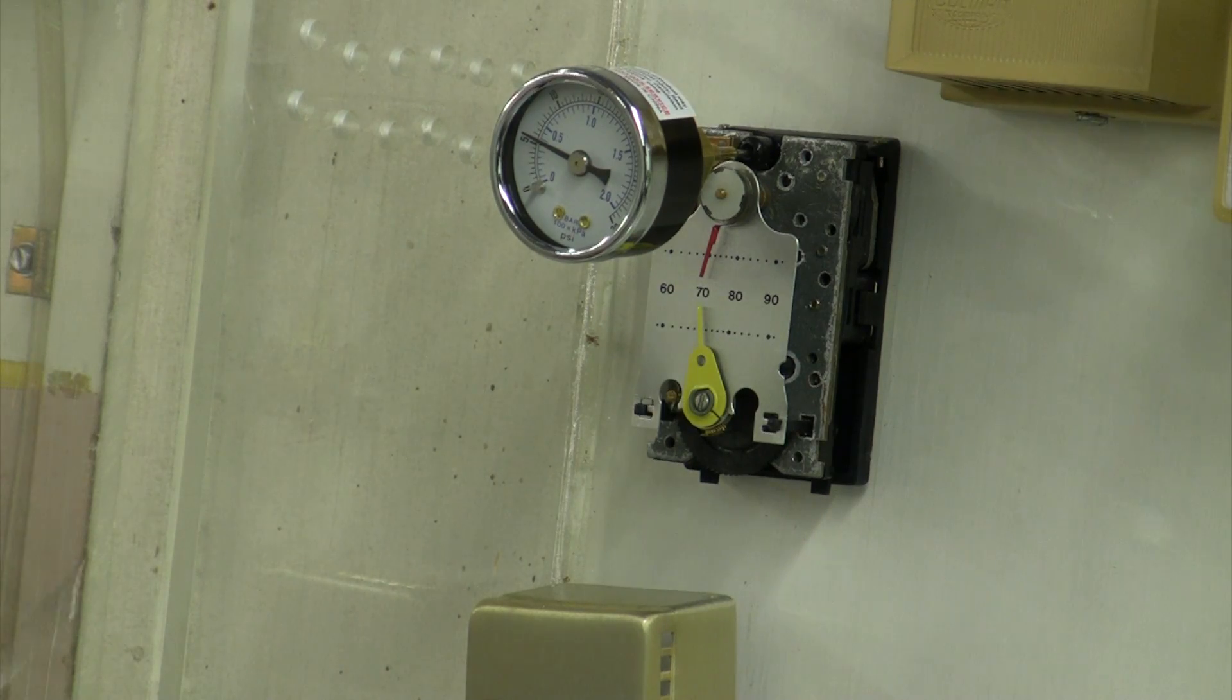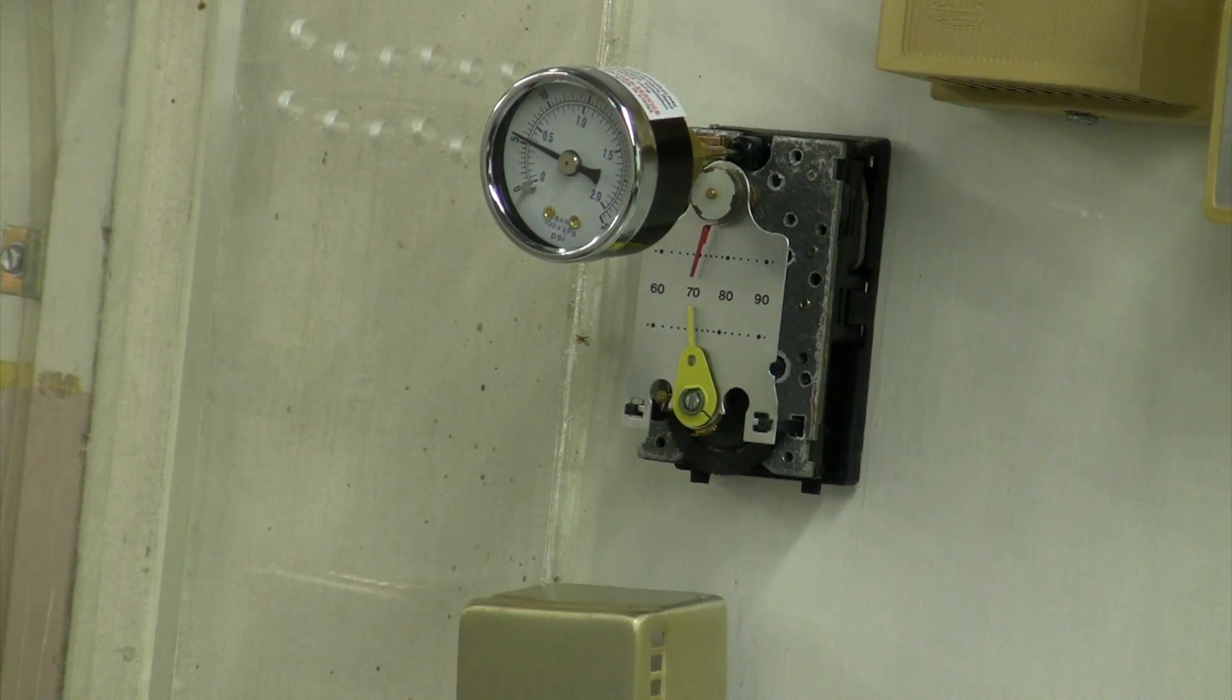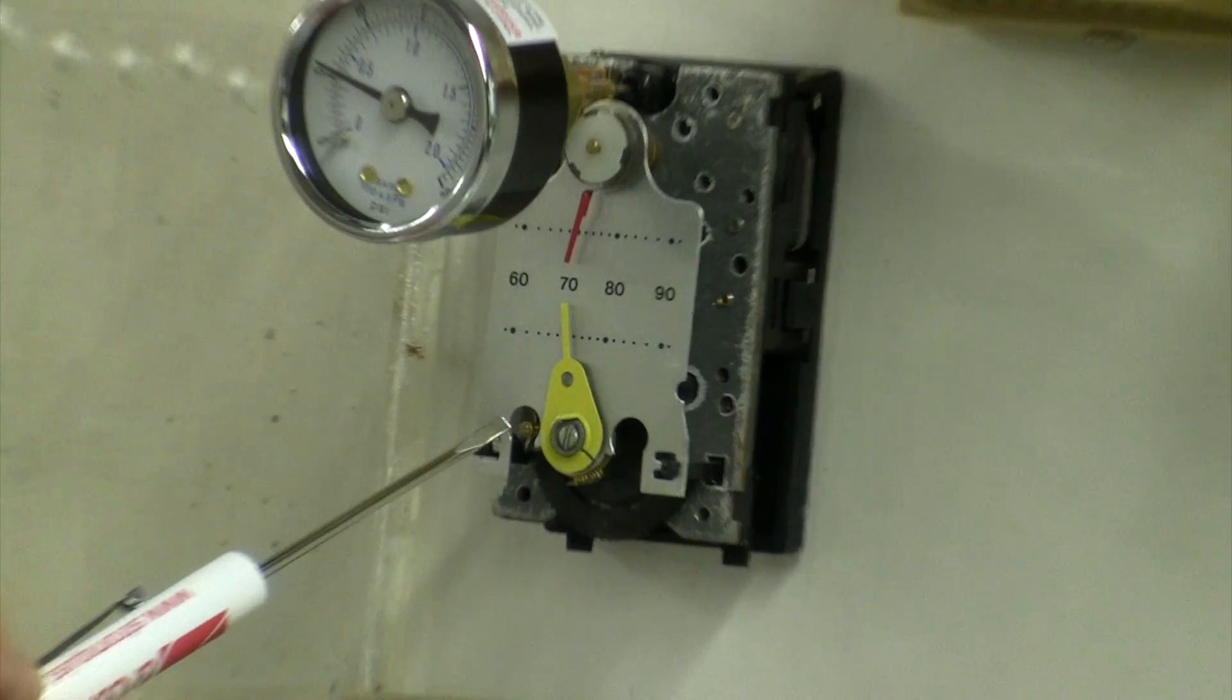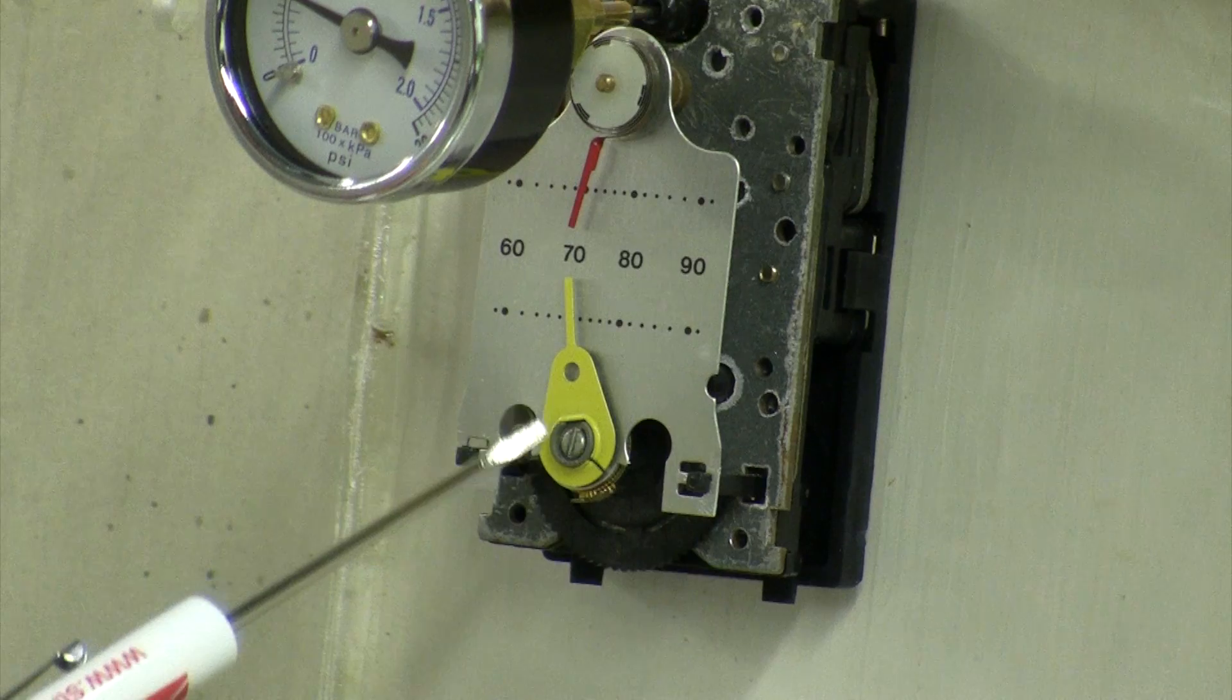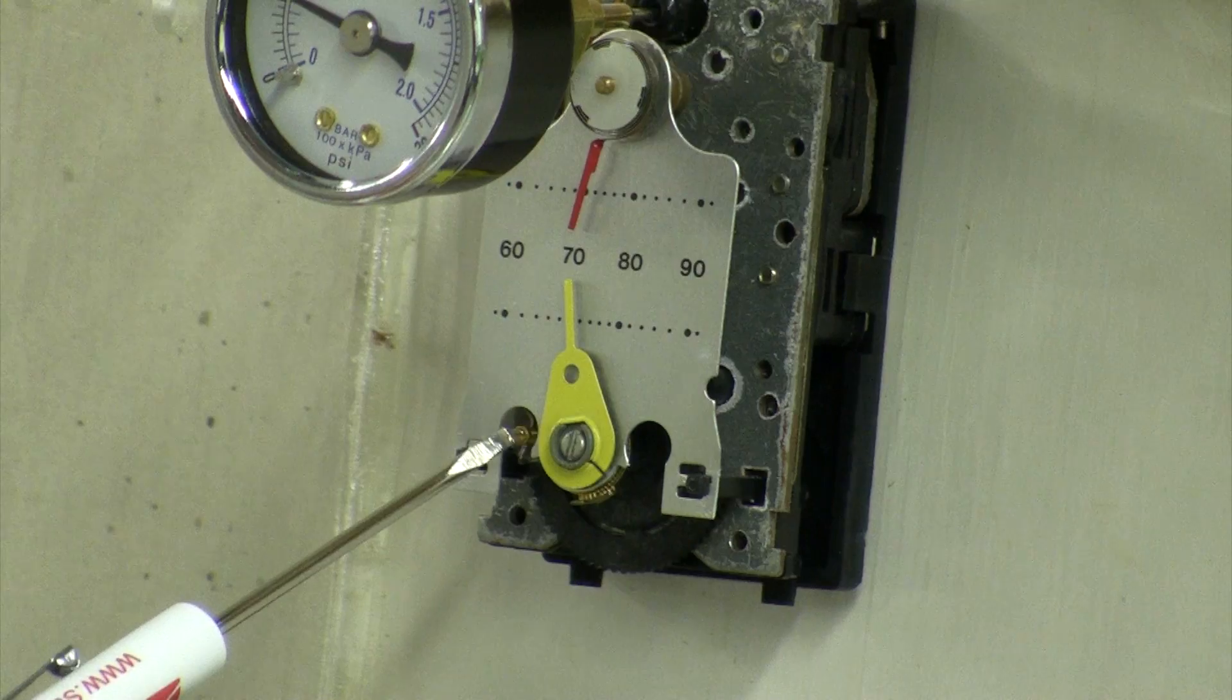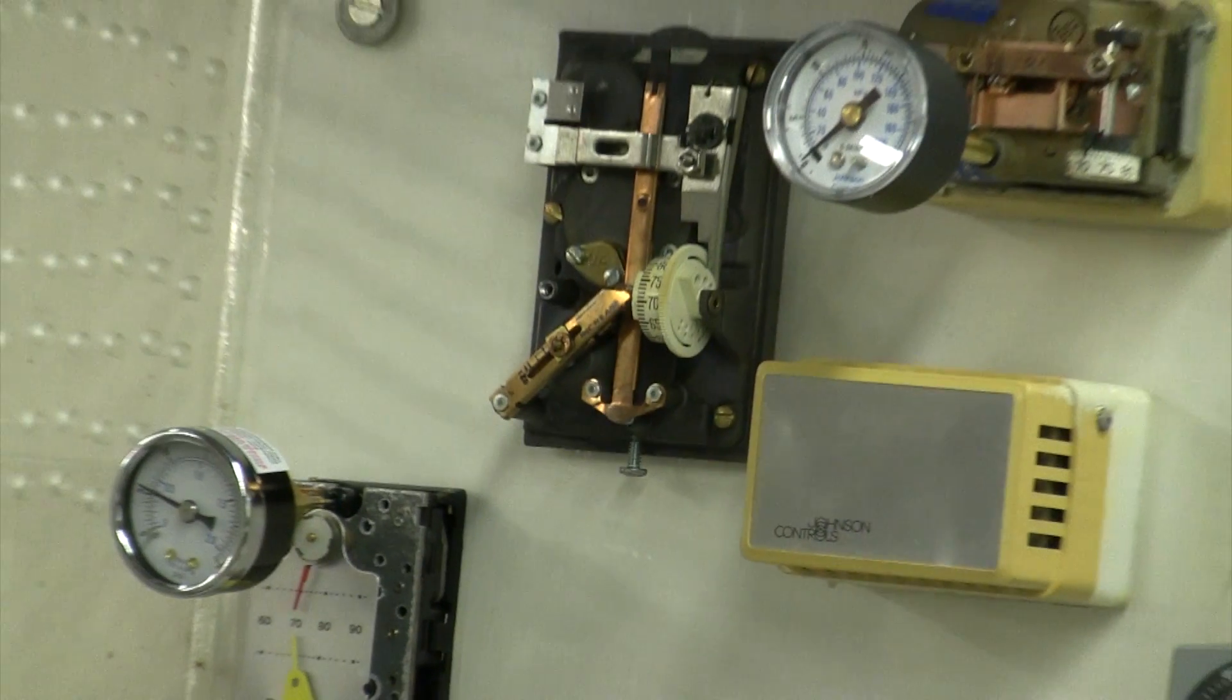The key to calibrating a pneumatic thermostat is to know where the calibration screw is, and it varies for the different brands. The Honeywell calibration screw is right here, just to the left of this set point indicator dial, and it's a little flat head screw. Let's take a look at the Barber-Colman.